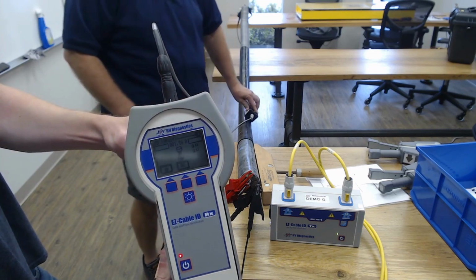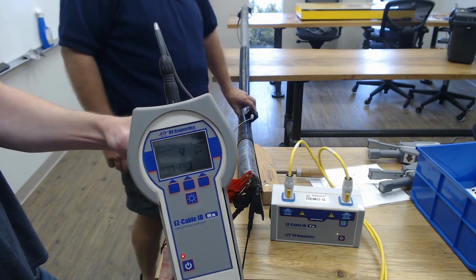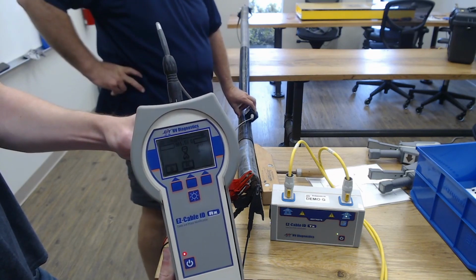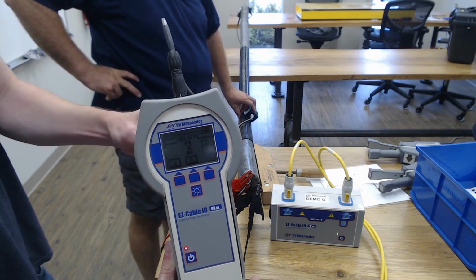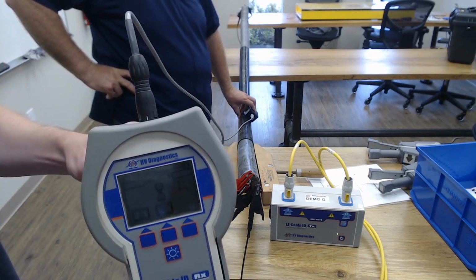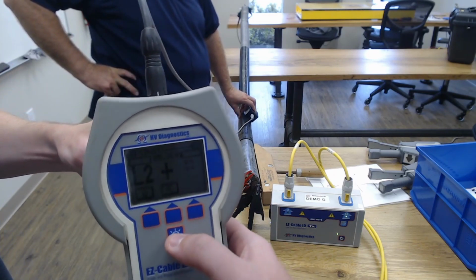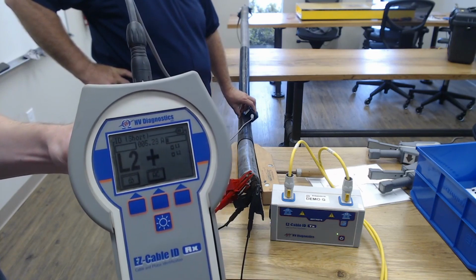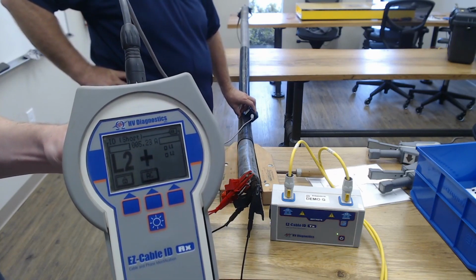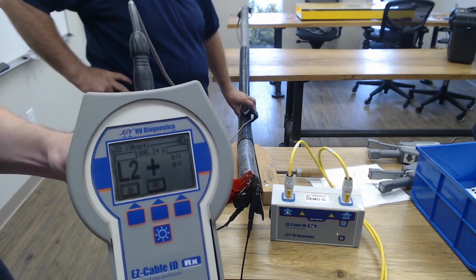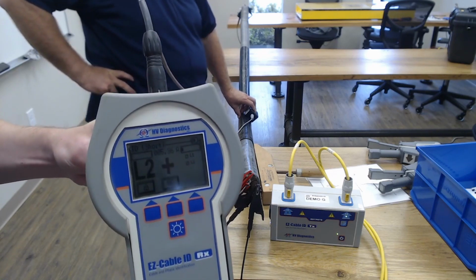Now, as I move it slightly around the cable, we should start to see L1 and/or L2. Can you get a better shot of that? You're not quite getting it right, Cody. No, you can't see it properly. There we go, that's better. So there we have L2. What's the current there, Cody? 5.24 amps. All right. So that's quite a big current.